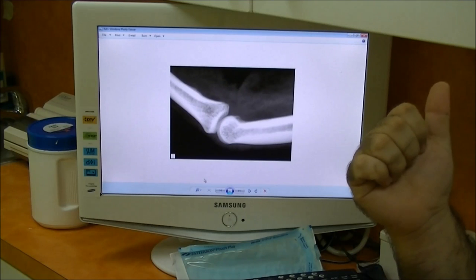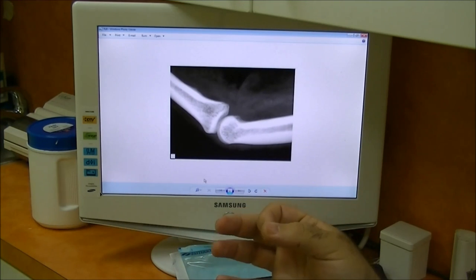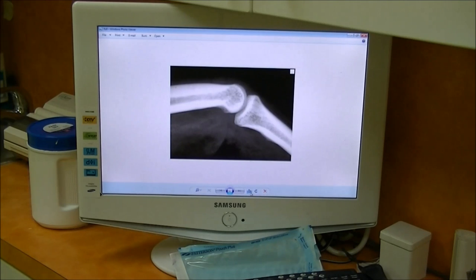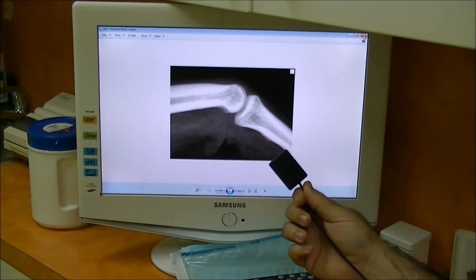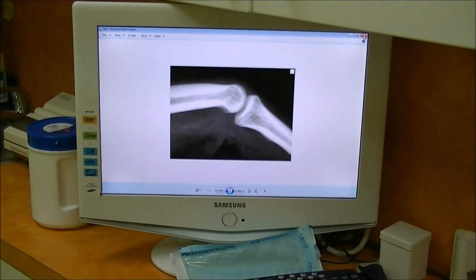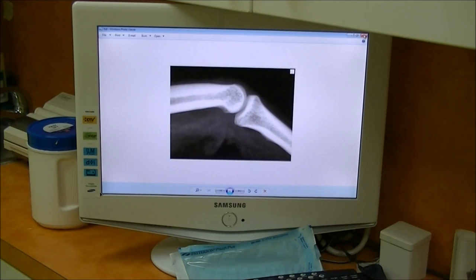We got our x-ray of my finger — there it is! No chemicals, and we didn't have to go through a developer. Once the system was set, it was actually a 0.1-second shot — a very small x-ray. And there's my knuckle. It's good-looking bone! All the records are stored in the server and the machine — everything done digitally. There are other models, bigger ones and multiple other companies, but this is the one this office uses and they were kind enough to let me demonstrate it. Thank you for watching — enjoy my knuckle — and that's how digital x-ray systems operate.